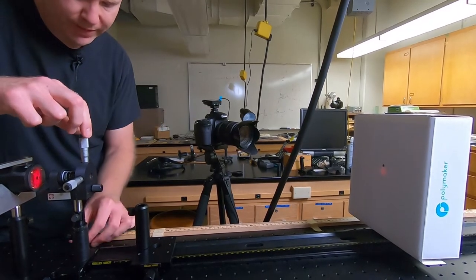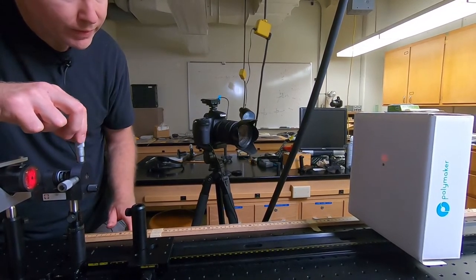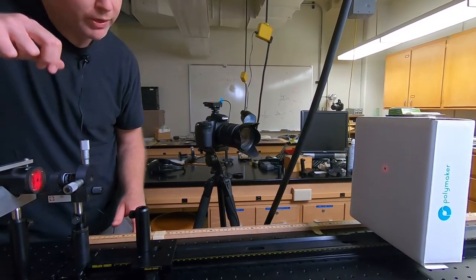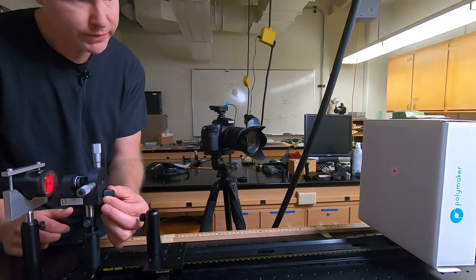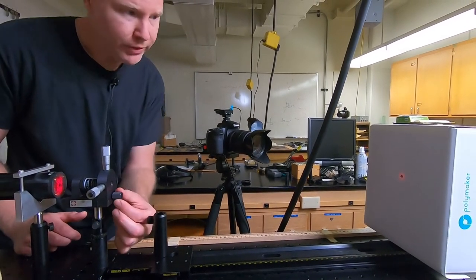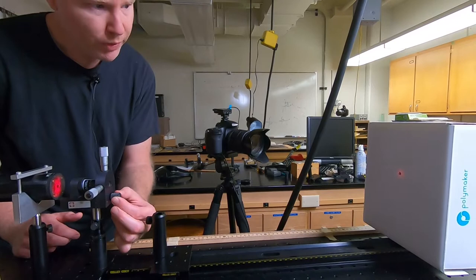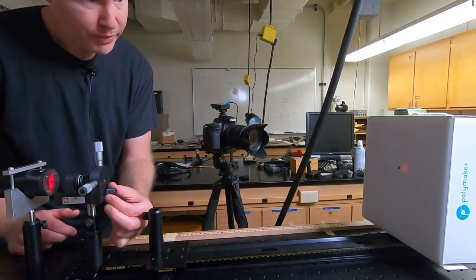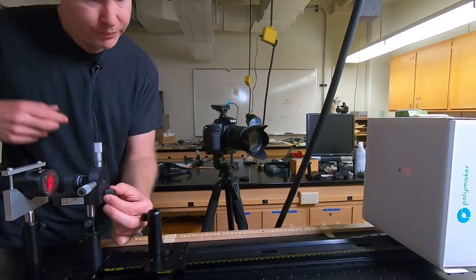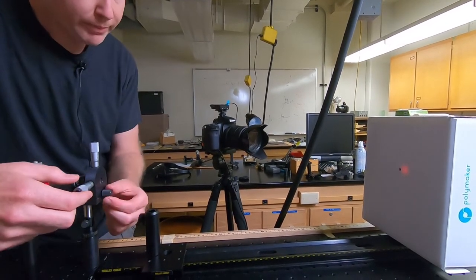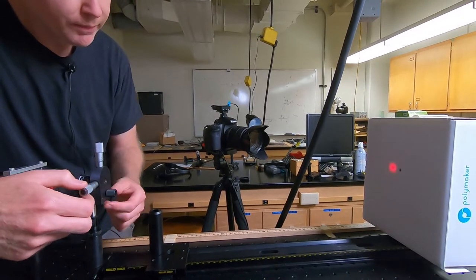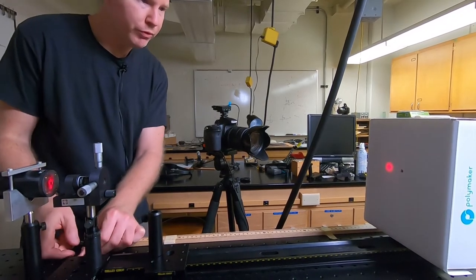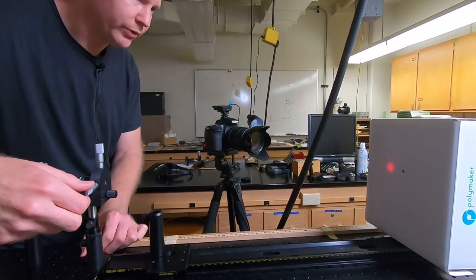Okay, so I've locked it in and the maximum brightness occurs pretty close to where I want the spot. Now I will adjust the focus. By adjusting the focus, two things should happen: one, the spot should get brighter as long as it's correctly centered; and two, the spot should get cleaner. So every time I adjust the focus, I have to refine the brightest position and maybe even readjust the X and Y locations here.